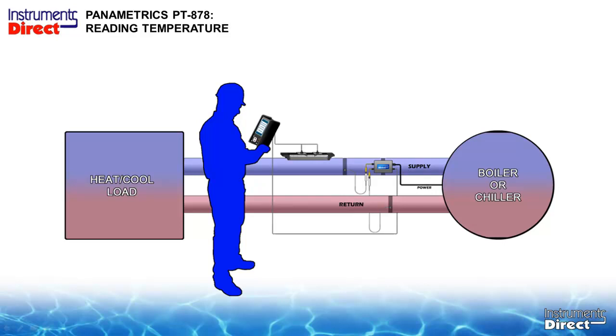It's just a closed loop system. We basically have a boiler or a chiller tied into a heat or a cooling load, in a closed loop system. And so basically you only need to monitor flow on one of these loops. So we put the flow meter on the supply line, and we'll put a temperature sensor on the supply line and a temperature sensor on the return line, and all that data comes back to your meter. And then the meter will calculate BTU. It's pretty neat.